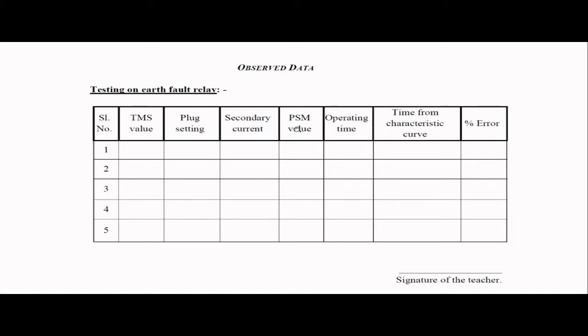Then the plug setting multiplier value. Now, what is called the plug setting multiplier? This plug setting multiplier is nothing but the secondary current divided by the plug setting. Okay, we'll discuss this later definitely. Then this is the plug setting multiplier value.